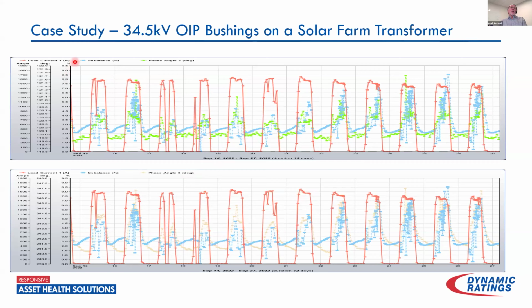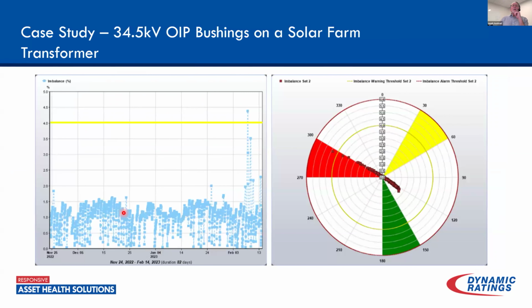I'm seeing it both on the imbalance and on the phase angle, basically on two bushings: my B phase bushing, my phase 2 bushing, and my phase 3 bushing. But again, it seems to be load related, and it goes away when we're not generating. So that prompted me to take a look at the data. What if we start isolating data, looking at it in a loaded condition and in an unloaded condition?